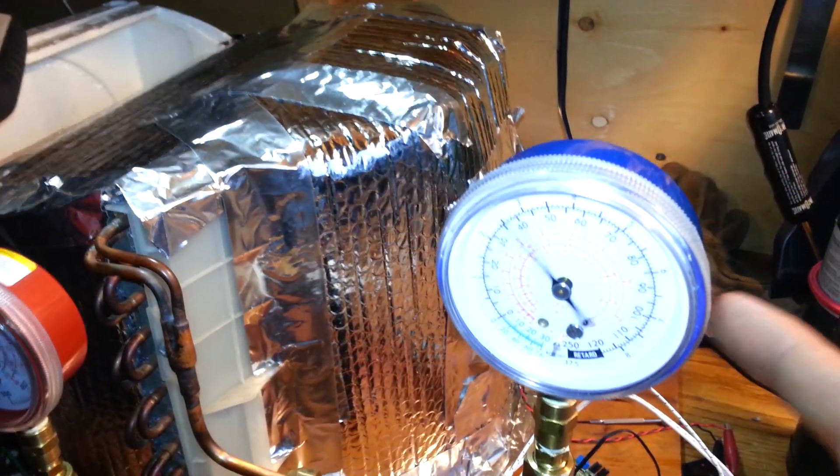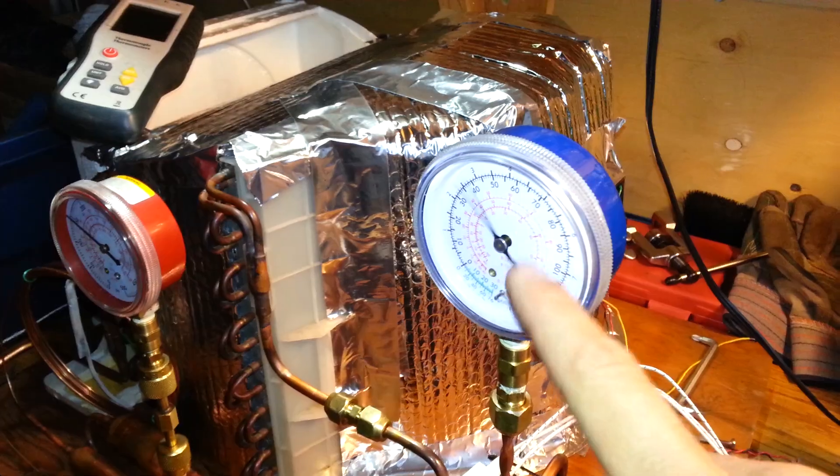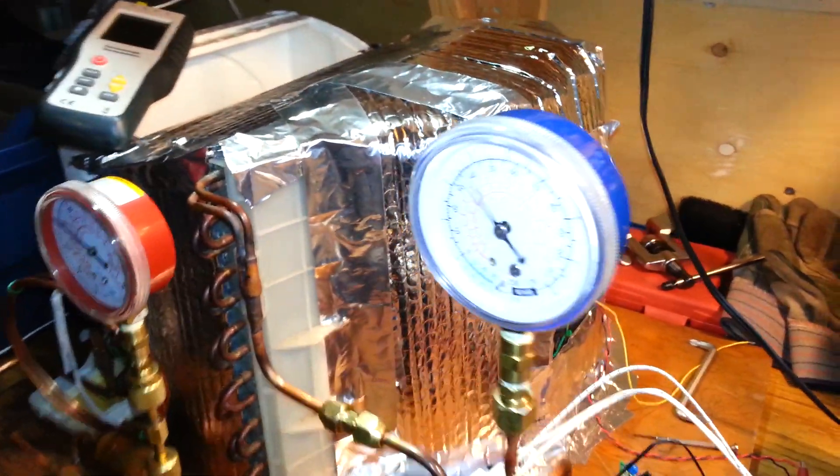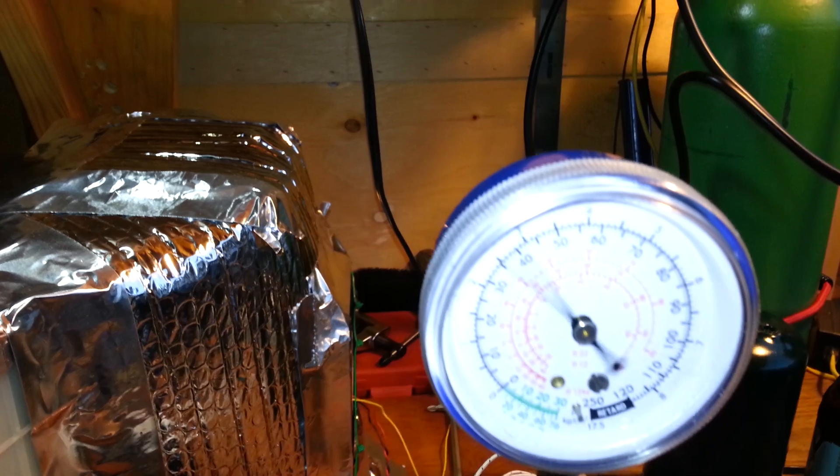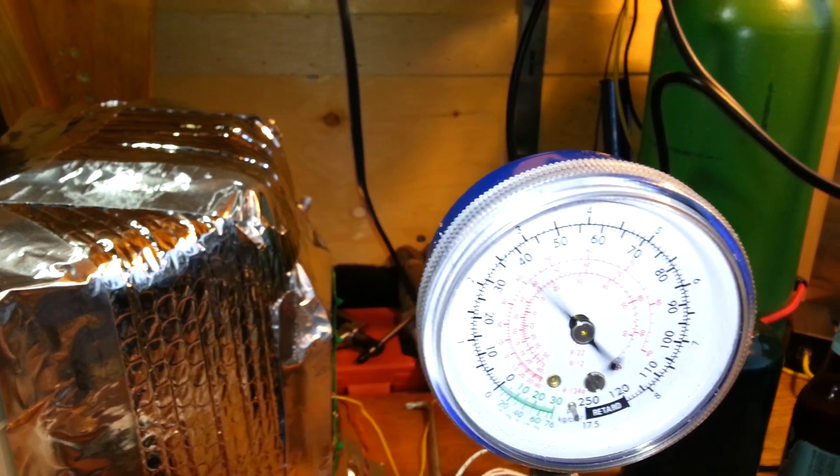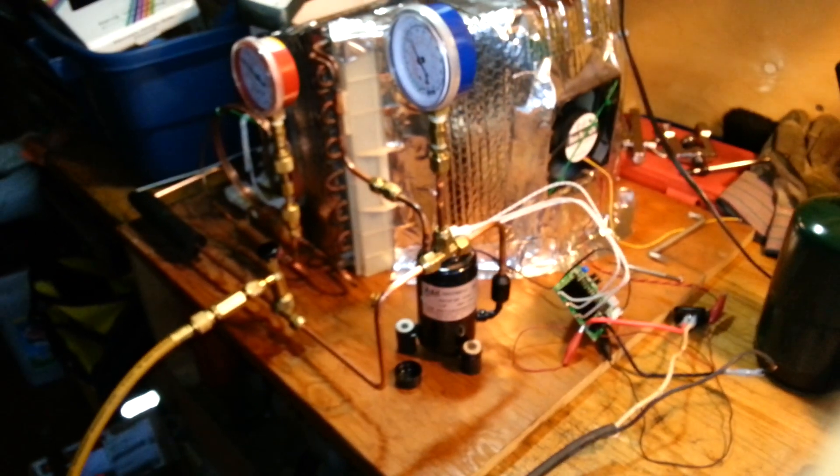Still got some fluttering. I might not be able to get rid of that entirely without going to a glycerin-filled gauge. But it's a hell of a lot better than it was. I was getting 30 psi or so in range, but it's relatively easy to read now. Thanks for watching.